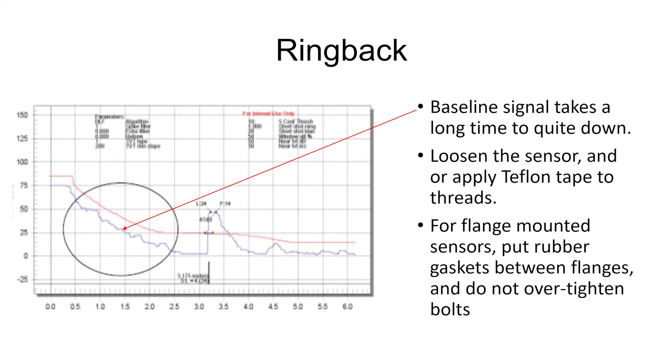With ringback, the sensor is too tight and for the threaded mount ones where you have the one inch sensor threaded to the conduit too tightly or in a flange mount, if the flange bolts are too tight, what can happen is it's like hitting a wine glass with a fork. It pings and it doesn't quiet down for a little bit. So it creates noise, wants to listen for the echo, but it's still ringing itself. Therefore, we don't know where the level is.